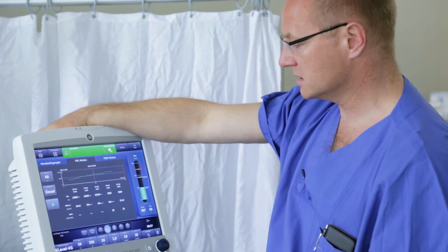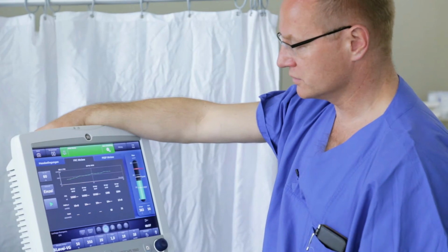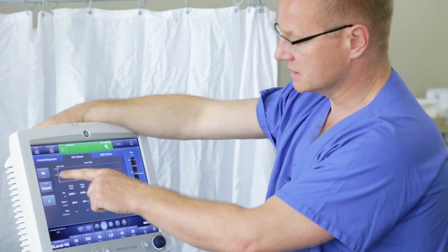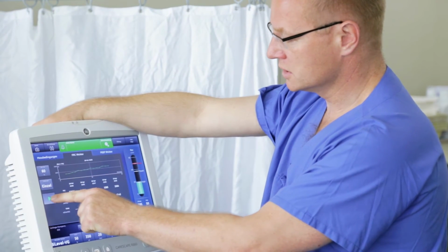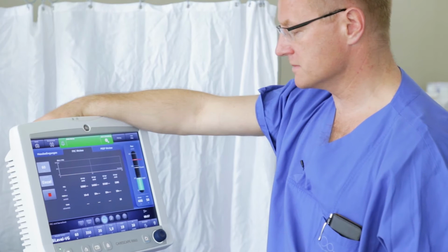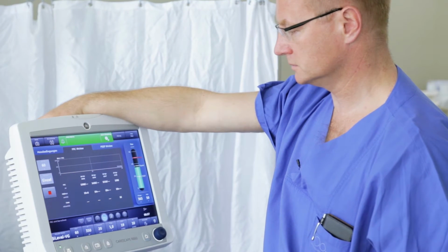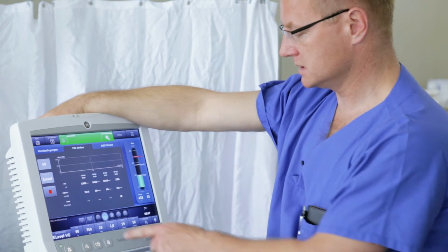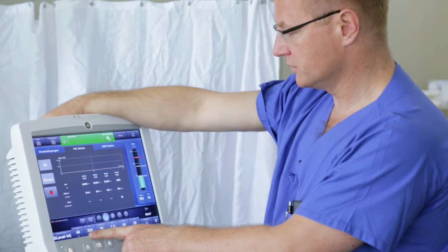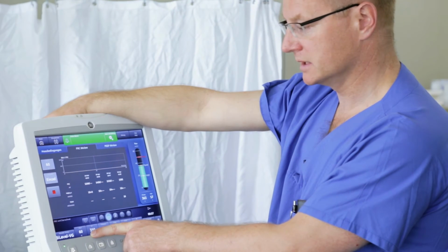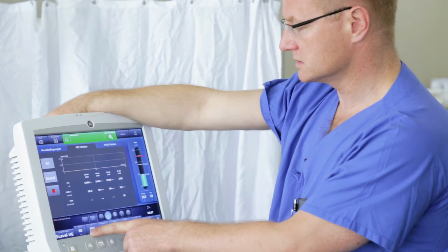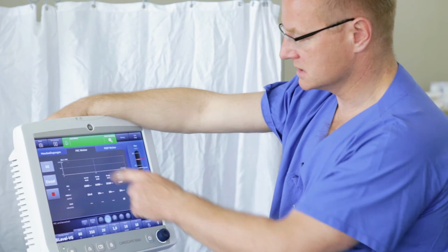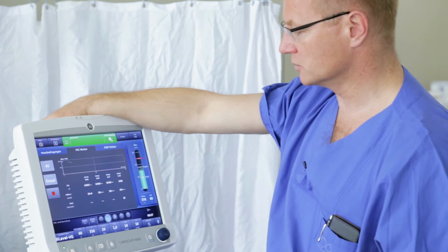With the aid of FRC in-view, I will now perform a single measurement, 50% oxygen, 10% change, single measurement. I will press the green button and the measuring will begin. Down here you can see that the device has now changed the inspiratory oxygen concentration from 50% to 60%. Thus the measurement is about to begin, and here we already have the first measured value, which is displayed as a green dot.